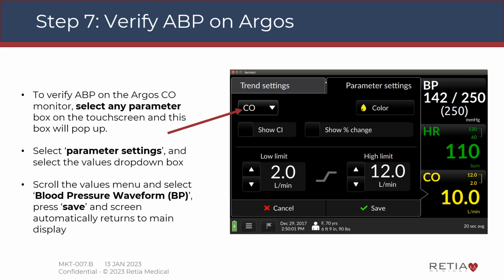Step 7. Verify ABP on Argos. To verify the ABP on the Argos cardiac output monitor, select any parameter box from the right-hand side of the touchscreen. Select Parameter Settings at the top of the screen. In the parameter box with the down arrow, scroll down via the drop-down menu and select Blood Pressure. Press Save and the screen will automatically return to the main display. Please note that the ABP waveform will still be displayed on the Philips bedside monitor throughout this process.